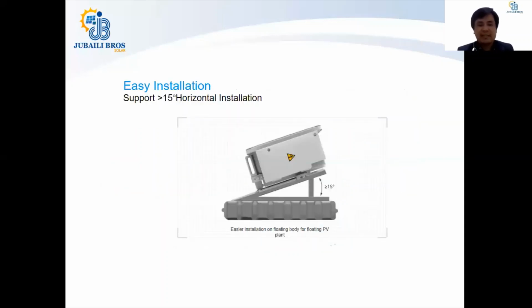Easy installation. The new 100 KTL inverter has been made so that it can be installed at a 15-degree angle from the horizontal surface. With the previous range of Huawei inverters, the inverter should be installed either vertically or 15 degrees to the backside from the vertical angle. But with these, you have the space of installing from 15 degrees backward from the horizontal up to 90-degree vertical. So with the more span now, especially when you are targeting floating PV plants, such an angle will benefit you in terms of occupying less area.